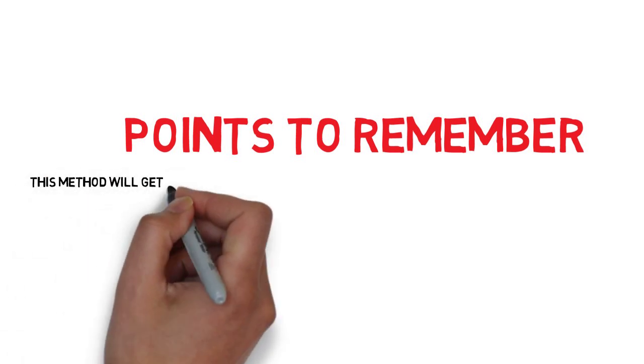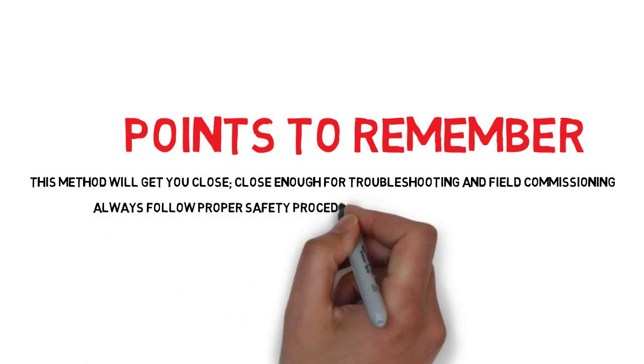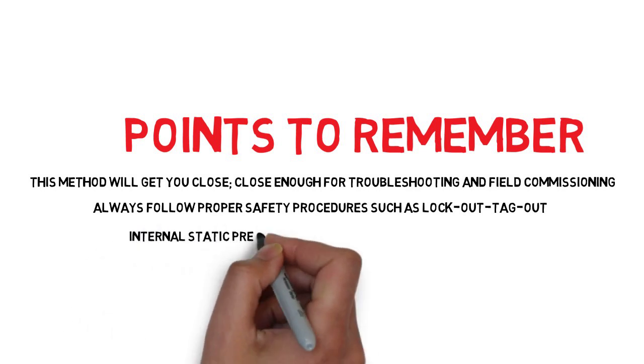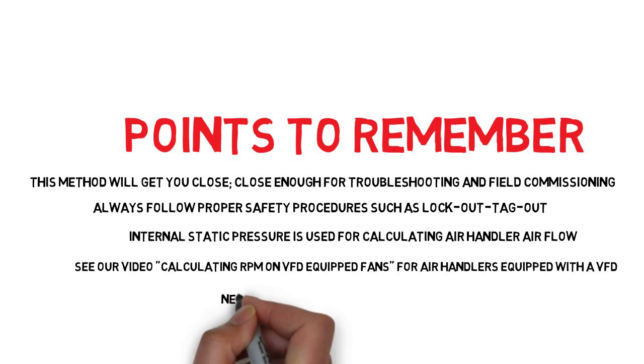Points to remember, this method will get you close, close enough for troubleshooting and field commissioning. Always follow proper safety protocol, i.e. lockout tagout. Always use internal static pressure for air handlers. Rooftops use external. And if you have a VFD, see our video on calculating RPM on VFD-equipped units. And, last but not least, never exceed the blower's maximum RPM. Bad things will happen.